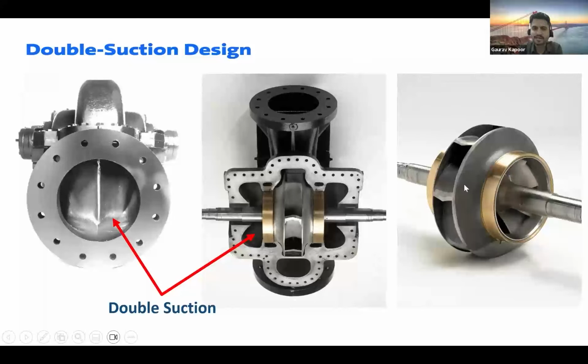It is designed and made in such a way that the water enters from two sides of the impeller and gets out one way. When this happens, all the forces balance themselves, because water is equally split into two halves, and by doing that you reduce a lot of forces on the pump, and the life of the parts and the pump goes very high. In general, the design life of split case pumps is around 25 years, and they have very low regular maintenance or failures if they are operated and maintained properly.